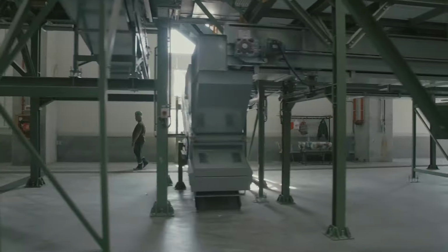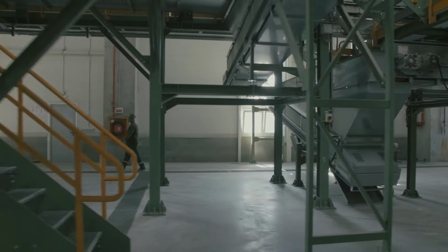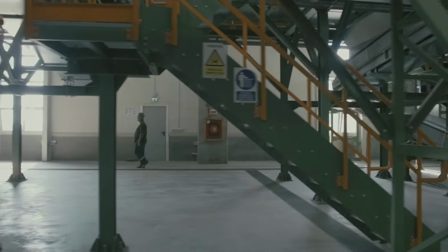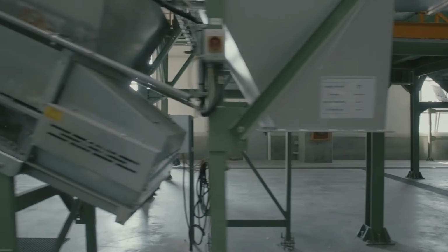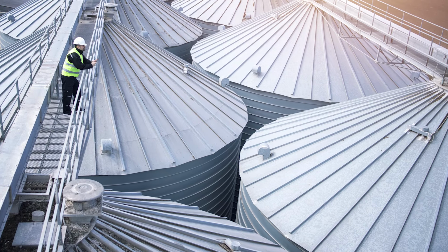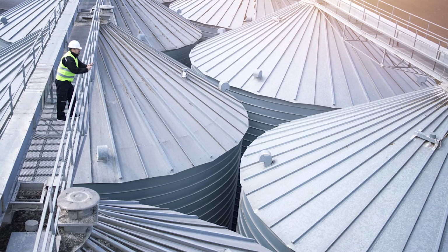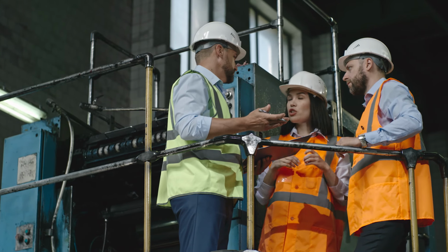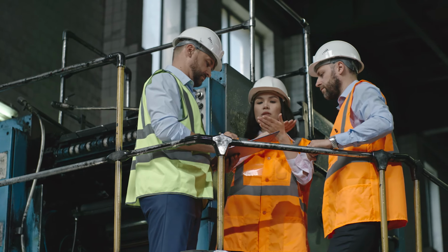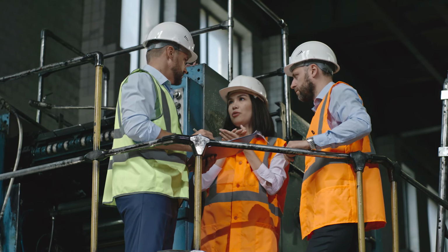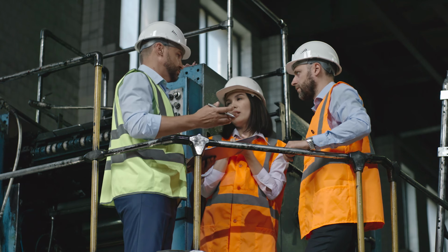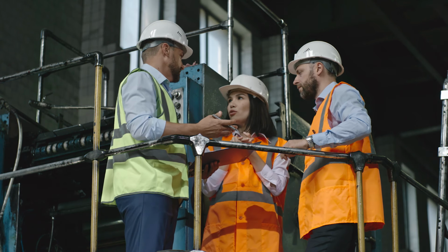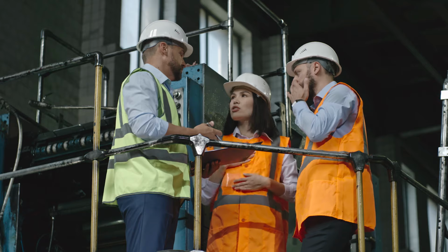A DHA should be led by a qualified person who has experience and knowledge related to combustible dust standards, combustible dust hazards, and the specific type of process that's being analyzed. You may or may not have the experience and expertise in-house, and you may need to use a third-party consultant. Even with a third-party consultant, it's imperative that a cross-functional team of engineers, EHS professionals, and operations and maintenance staff are used to ensure that the process is well understood and that all hazards are correctly identified.